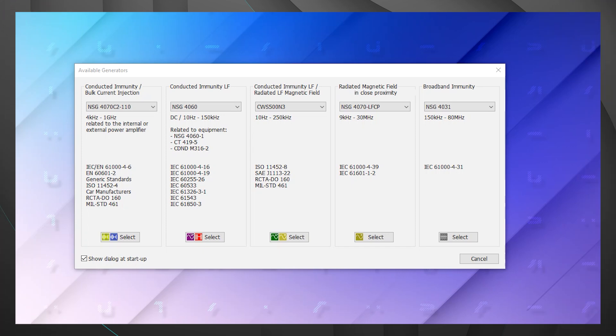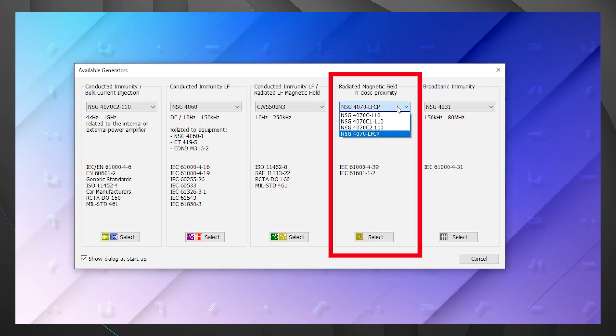Here you're going to find the starting display for the ICD.Control software. You can see there are a few options here. What we're interested in today is the radiated magnetic field testing in close proximity, which is going to be the fourth option. You can see right now there's the NSG 4070 LFCP selected. We're going to hit that drop down and go to the NSG 4070 C2-110. Now let's hit select.